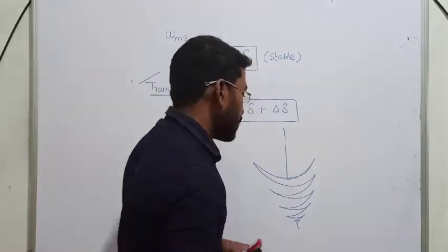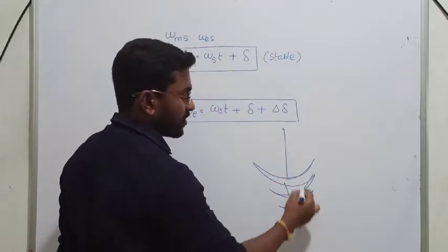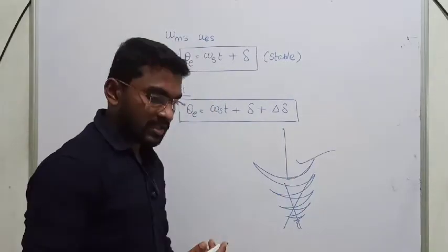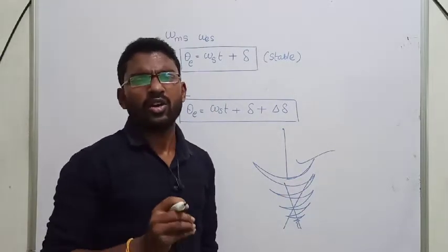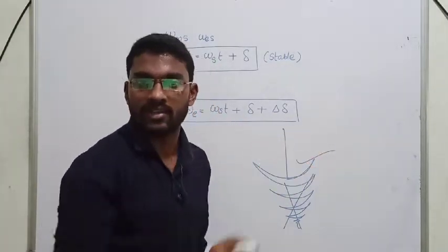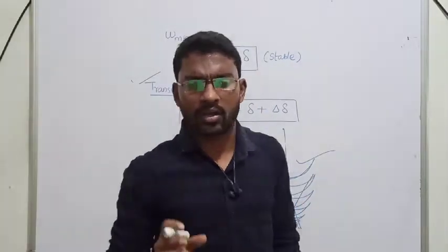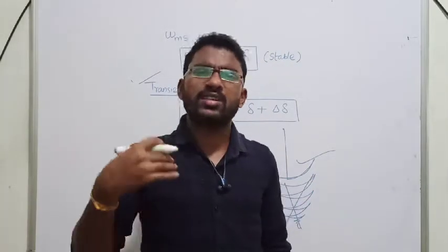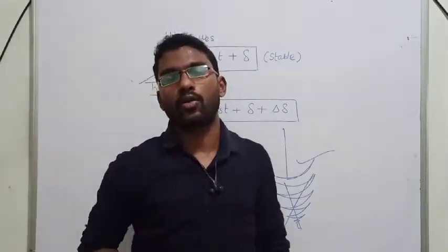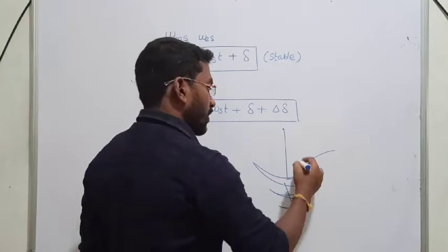Okay, so what is the conclusion here? But sir, how many swings are we going to consider here? We are going to consider only the first swing. Why? Because in the first swing, the effect is very huge, and then the swinging starts reducing and your system will slowly be stabilized. So to know the worst case, the maximum disturbance, for the alternator you have to go with the first swing. Okay, so let me go with the first swing.